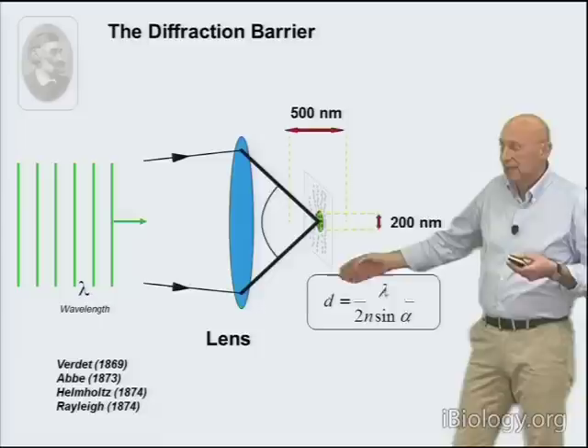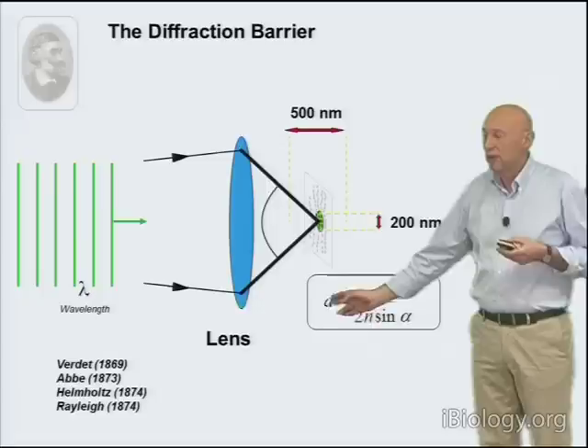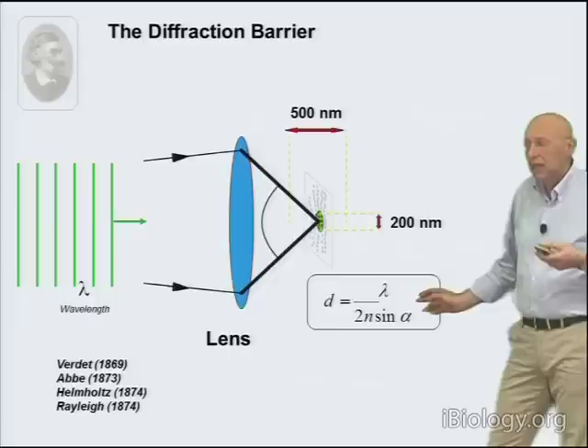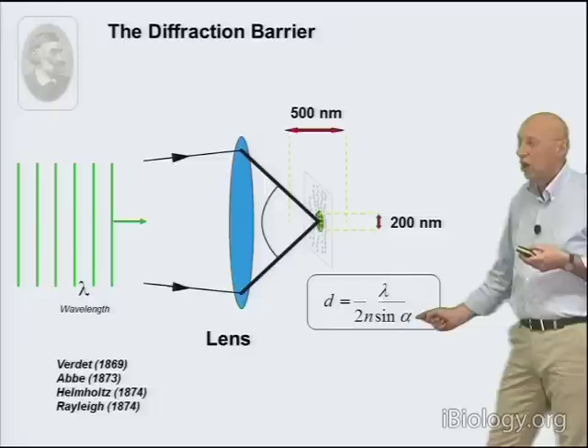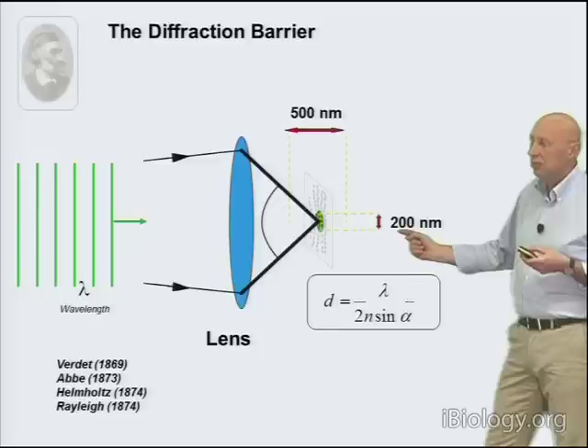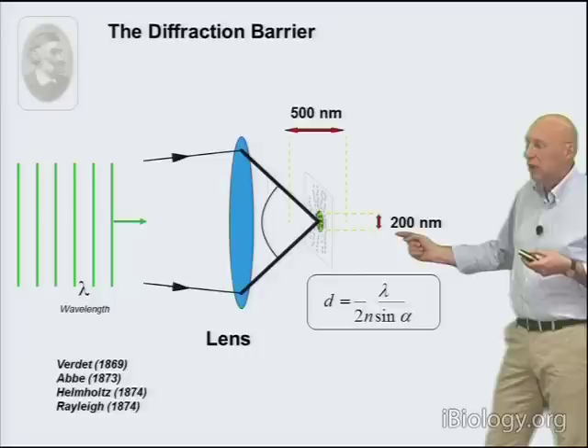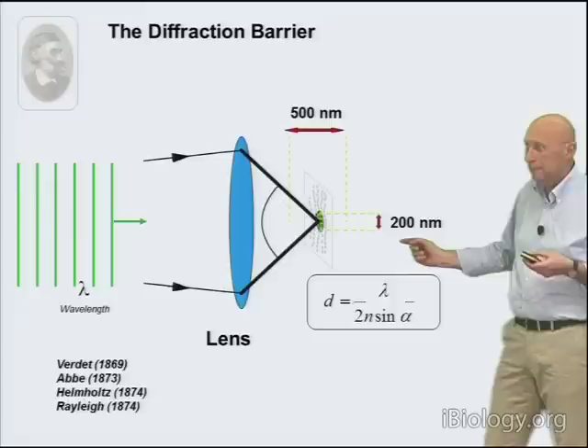The person who realized this was Abbe, who formulated the diffraction resolution barrier in an equation. Two features of the same kind, in order to be separated by a light microscope, have to be further apart than the distance d, given by the wavelength of light divided by twice the so-called numerical aperture of the objective lens. This value amounts to at least about 200 nanometers, up to 300, 400, or 500 nanometers. This is the reason why people have thought that a light microscope will not be able to do any better than that.